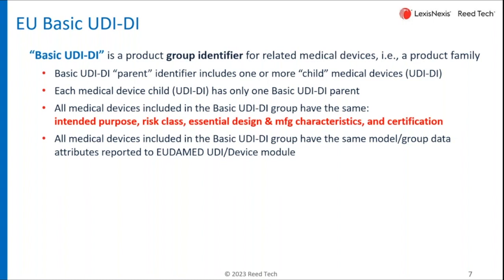There are some rules about how you create this. Things to remember: the intended purpose, the risk class, the essential design and manufacturing characteristics, and the certification — all of those have to be the same for every device in the group. In addition, there are some attributes reported into EUDAMED, and all those attributes have to have the same value for each device in that group.